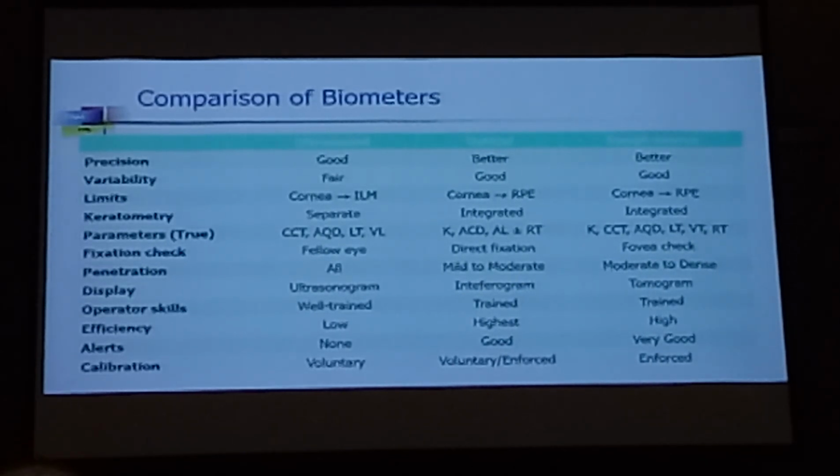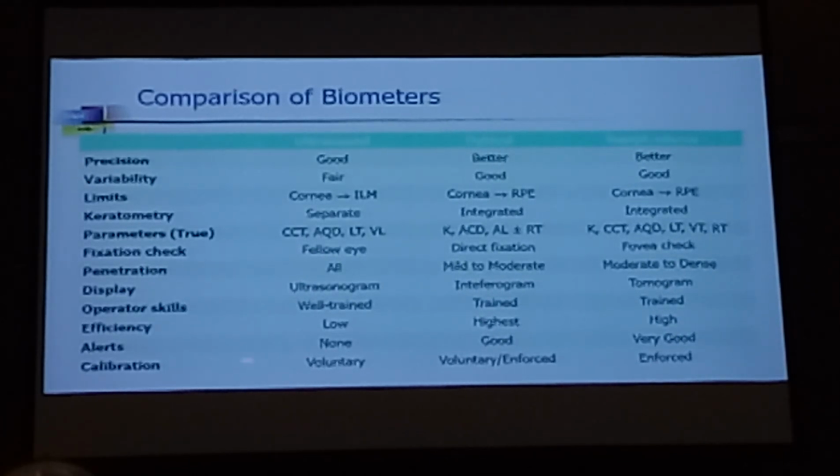What is the operator skill required? With ultrasound, the operator has to be very well trained. For optical, they have to be trained, but it's less operator dependent. Efficiency, of course, ultrasound is not very good, especially if you do immersion. Not too bad, but not too good. Optical and especially swept source is very good. Optical can be faster or slower, depending on the make. The modern ones will alert you to all kinds of situations. Ultrasound may not do so.